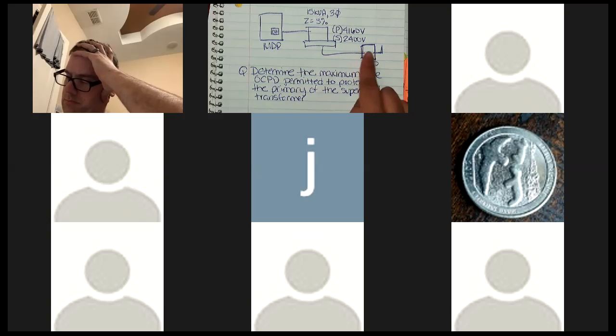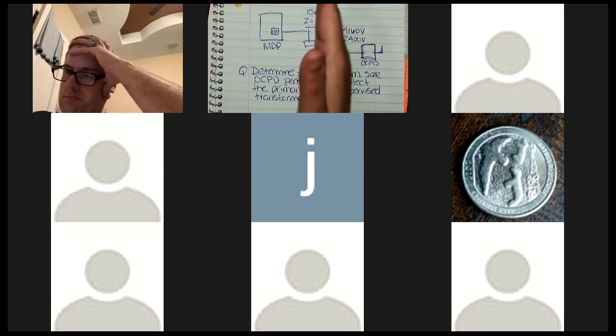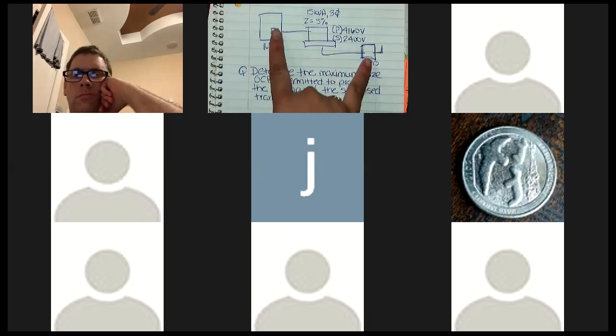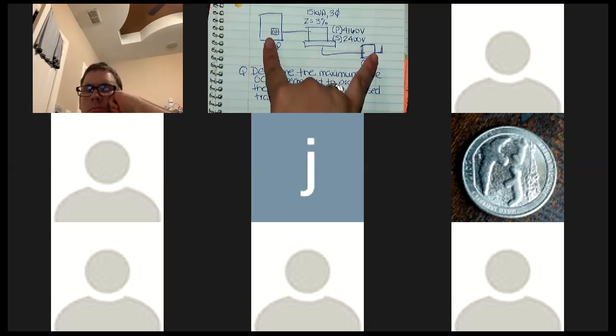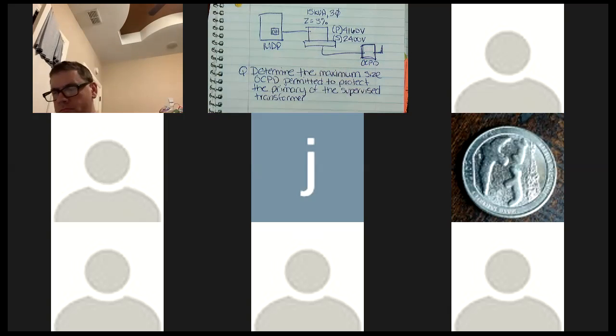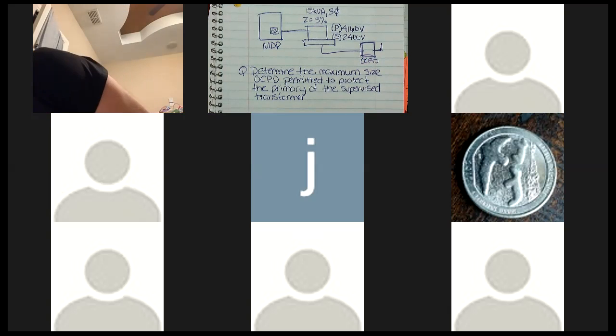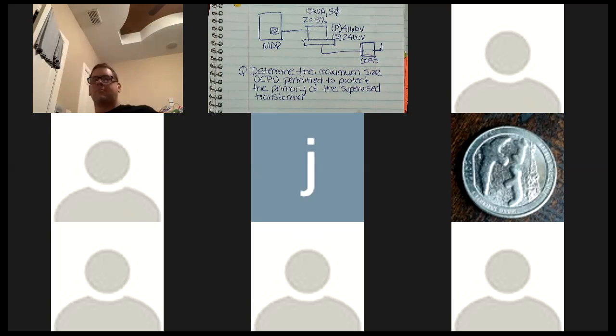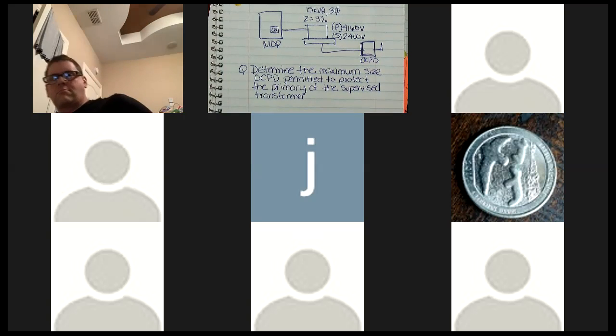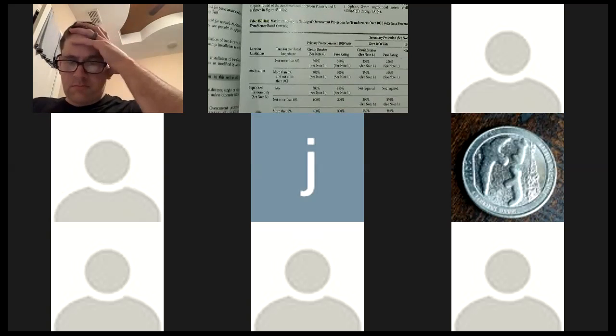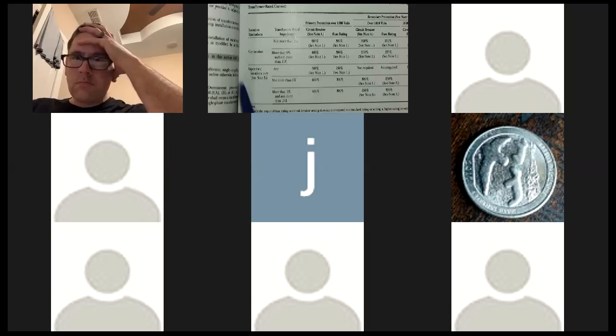Now, if it was a load or the wires were just hanging out there like in the book, then we could just do primary and focus on primary protection only. But here, I see two protections. I have my MDP and I have another disconnect right there. So in this case, I do have an impedance. I'm going to go with Table 450.3(A), right? And then it does say that it is supervised. So I'm going to go to the supervised column. Let me show you. Right here, I'm at supervised.